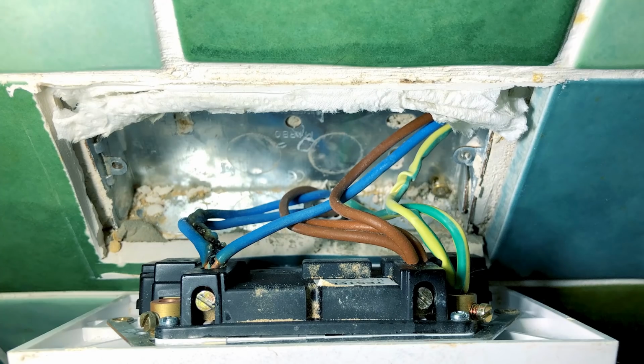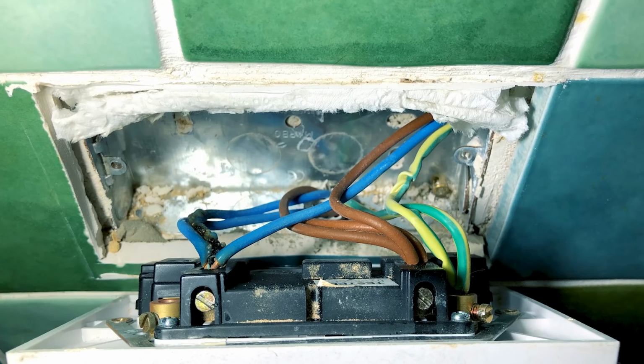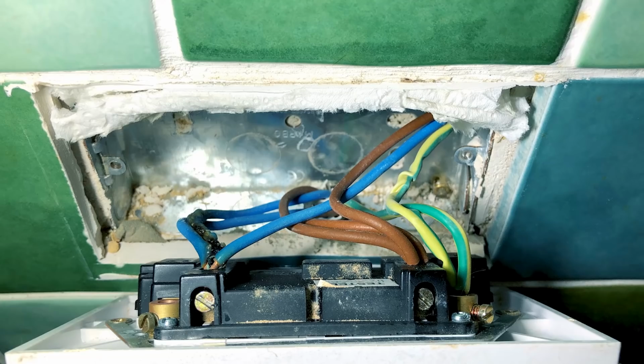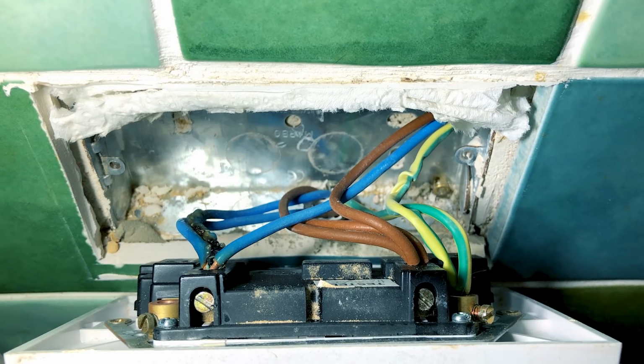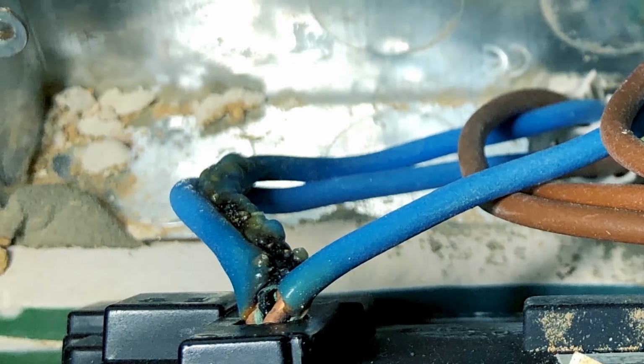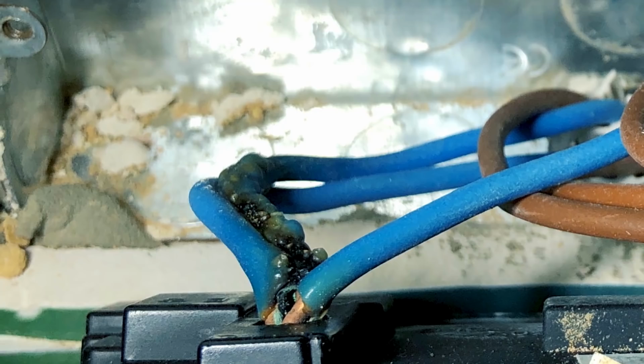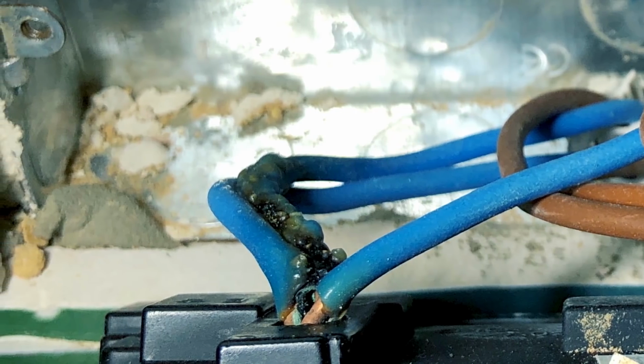So I decided to take off some of the other sockets as well, just to check that the fault hadn't caused problems elsewhere, and I was glad I did, because one of the sockets had started overheating on the neutral as well. You can see that bubbling and the black bubbles on the wires - that was from the neutral overheating.